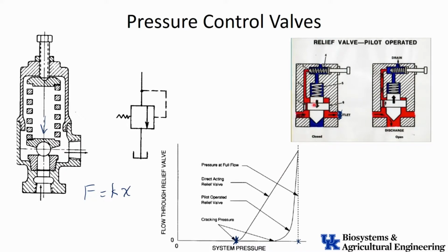But now we also have something else going on here. So we have a hole through this poppet, and that's on purpose. So it's a hole that allows this little wee bit of flow to get up in here, okay? And now the flow could go on up, and there's another direct acting relief valve. This is just a real small direct acting relief valve up here. But it's a real small port, real low flow, much smaller than what the main flow rate is in here. But this would be closed when we're below the system pressure.